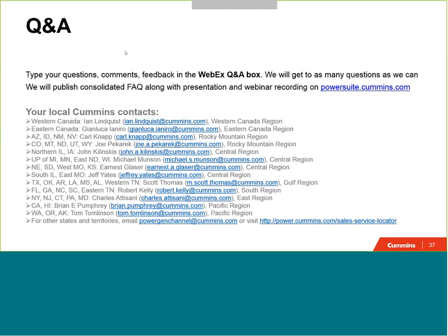What is the normal time run for factory tests with full load? Great question, and this definitely does depend on the generator set manufacturer. I would say that most generator set manufacturers run at least 20 to 30 minutes at full load at the factory. If you want to see it run for 30 minutes, don't rely on what you think most generator set manufacturers do. Call out 30 minutes at full load in your specification and hold the generator set manufacturer to that. They should be able to provide some sort of indicator of compliance with your particular requirement.